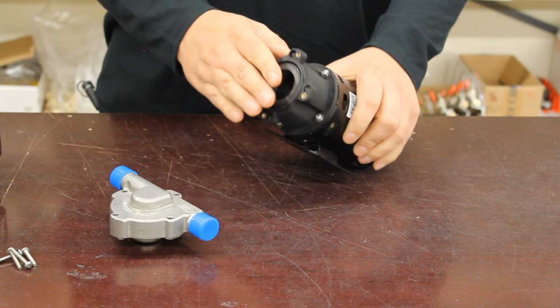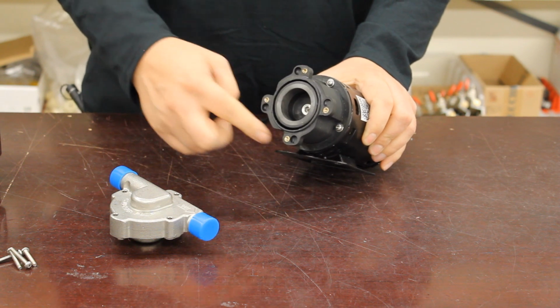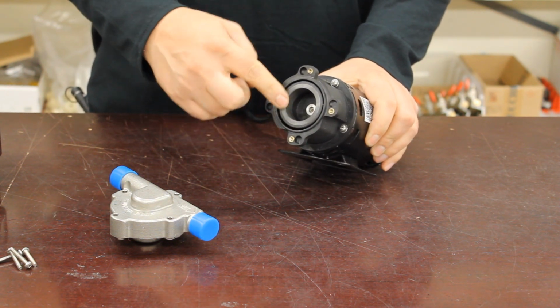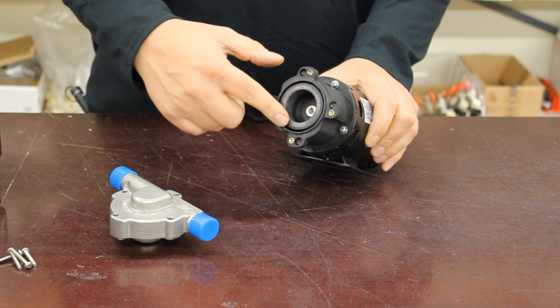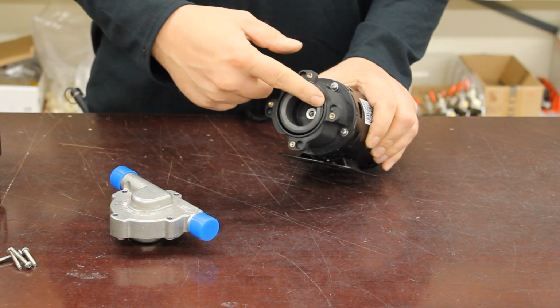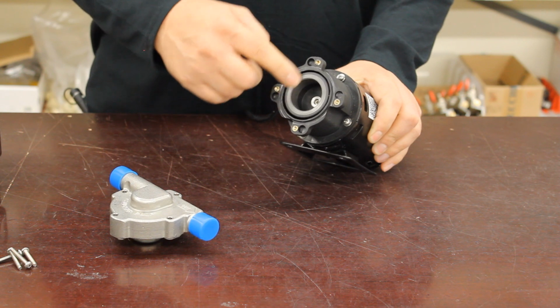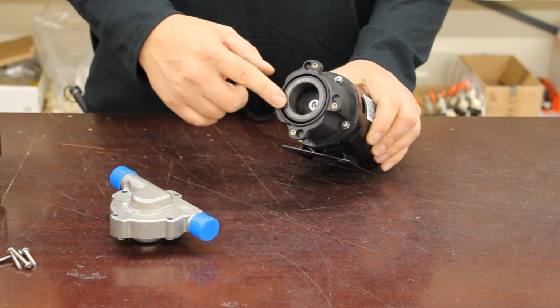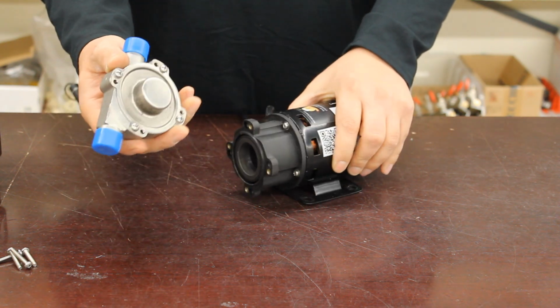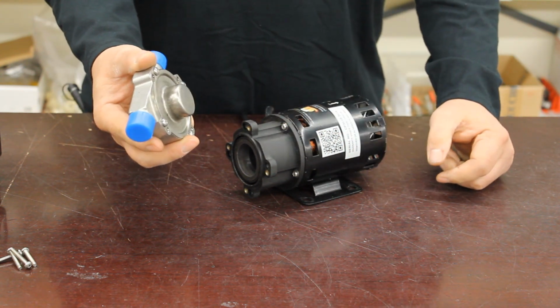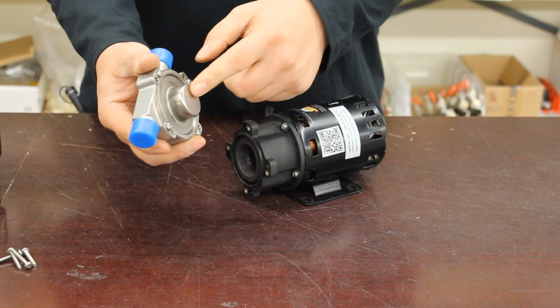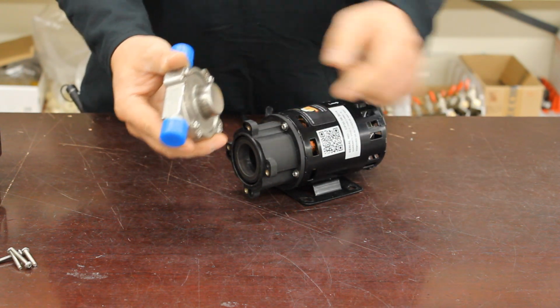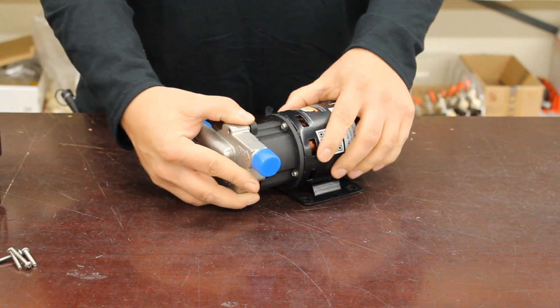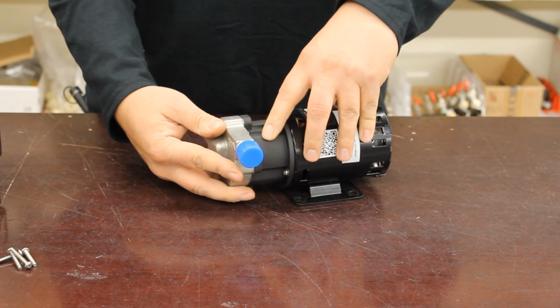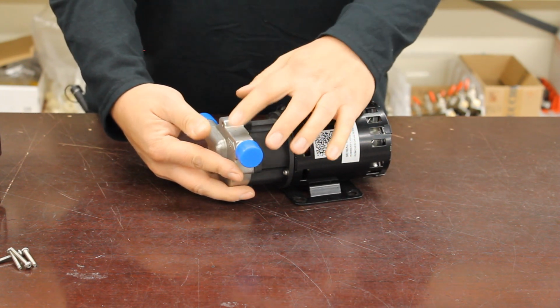Now inside the mounting ring or the mounting bracket, you'll see the cup magnet. Now this cup magnet is solidly attached to the motor shaft on the motor, and when the pump is running, this cup magnet is spinning. Now the impeller is on the inside of this head assembly, and there's also a magnet that sticks into this bump out in the back of the head. So when you put this together and the motor's turning the cup magnet, it in turn turns the impeller within the head. That's why it's called a magnetic drive pump.